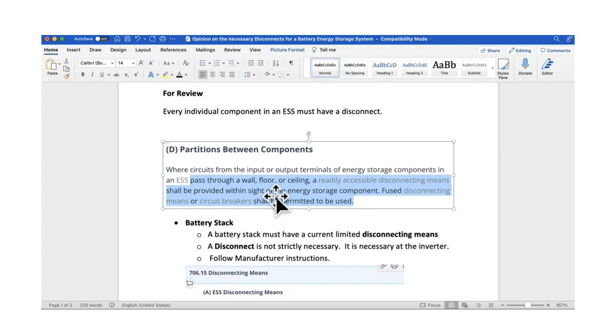And so I would look at this one like, let's say that for some reason you had your battery inside and your inverter outside, then you would want to be able to have a disconnecting means by the battery. So that would be maybe a fused DC disconnect, something like that. Because if it's DC, you're very unlikely to be using circuit breakers. It might even be debatable, since it's an equipment disconnecting means, that you could use the button on the LG Chem battery itself, because the LG Chem battery doesn't really have much in the way of a short circuit current rating because you're connected to a DC to DC converter.